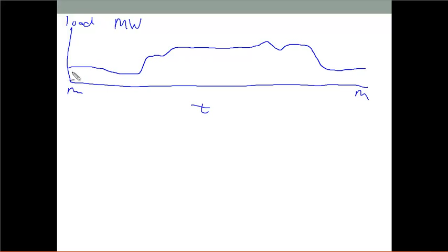And so say here in Jacksonville, let's say down here, maybe it's 1,000 megawatts I need to make. Okay. And maybe up here, my peak for the day, let's just say that was about 1,600 megawatts, okay? So somewhere, my base load, we call this the base load, the lowest that you need to generate, say somewhere around 1,000 megawatts. So you need to be able to generate 1,000 megawatts all the time. You need to be able to generate about 1,600 megawatts in the afternoon, okay?